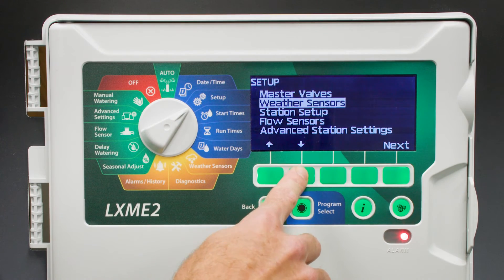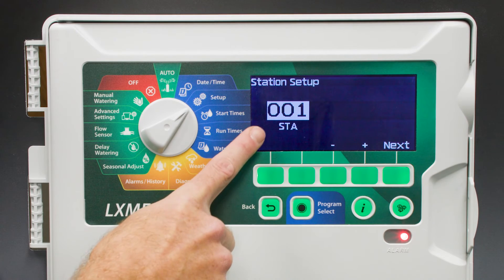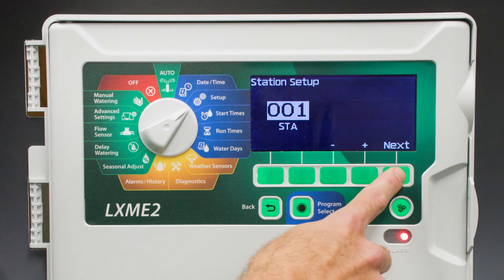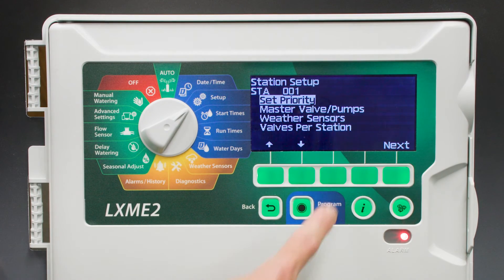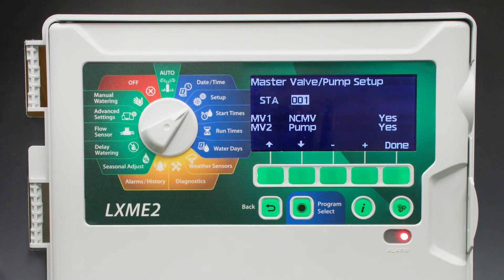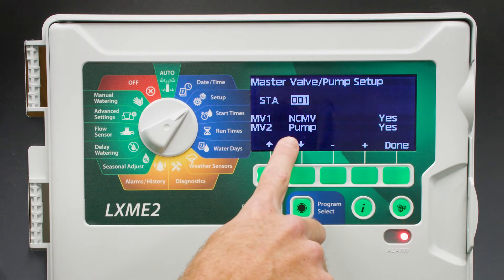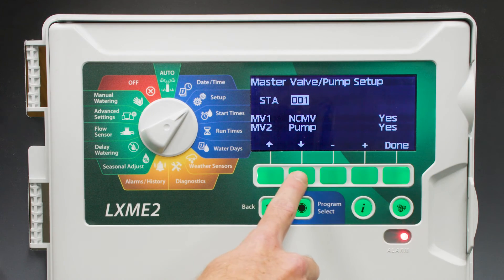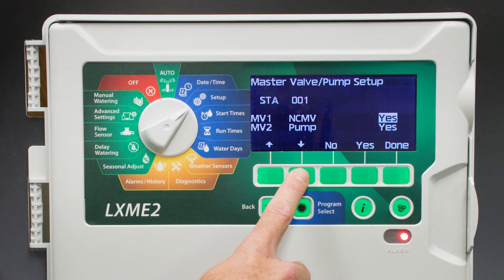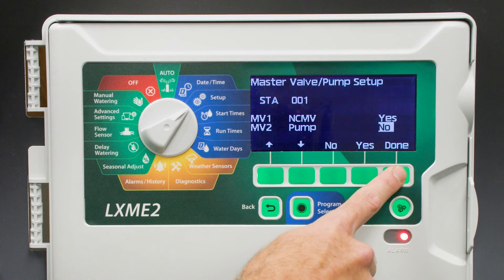Next, we'll toggle down to Station Setup. We're going to set up Station 1 as a drip zone, so we want to run the master valve, but not the pump. Select Next, toggle down to Master Valve Pumps, and we see that Master Valve 1 and Pump are both set to Yes. In this scenario, we want the master valve to turn on, but we don't want the pump to turn on. So let's toggle the pump to off. Select Done and go back.